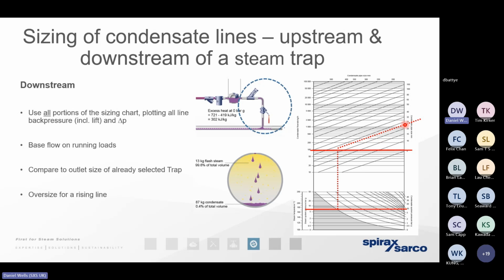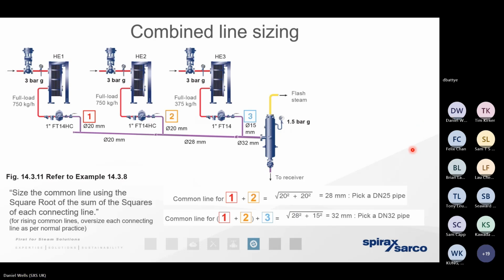If we'd assumed that it was a non-compressible fluid at all pressures, then we wouldn't have allowed for that expansion to take place, and the pipework would be significantly undersized. This is a very, very common error, especially if we're working with engineers who may be far, far more familiar with water-based systems that haven't allowed for that phase change.